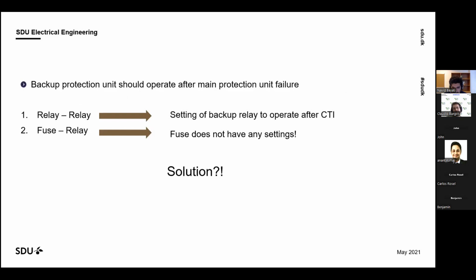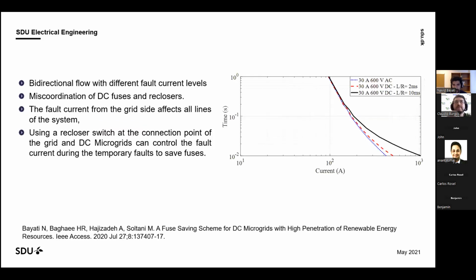Also, we need some coordination inside of the microgrid. What's the meaning of the coordination? To make sure that if you have, for example, a fuse for every load and a relay on the main side, and you have a fault inside of the load, for sure the fuse should act first. But if we move from islanded mode to grid-connected mode, the settings between them will change. So we need some adaptive coordination between the fuses and reclosers. So here we proposed a method for changing them, for providing some adaptive protection of the fuses.